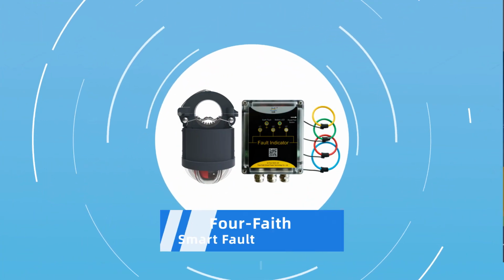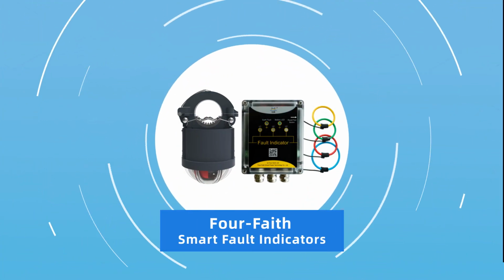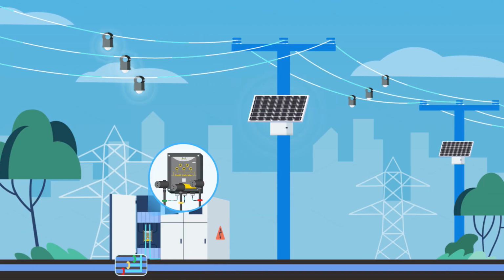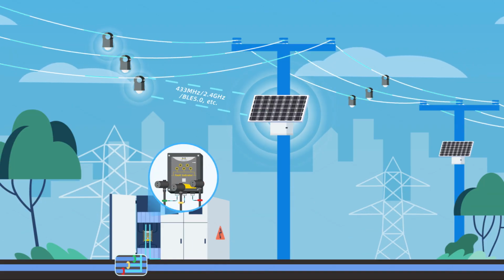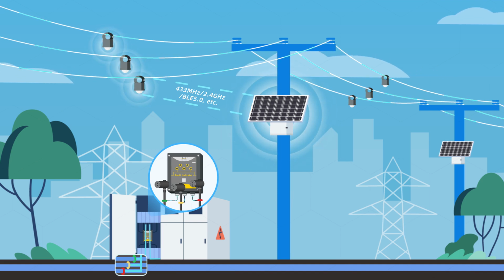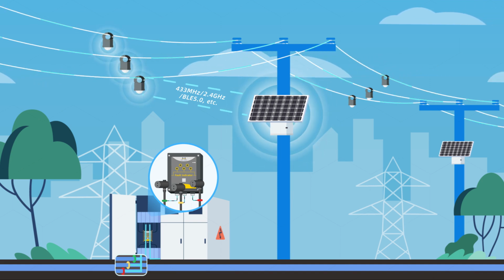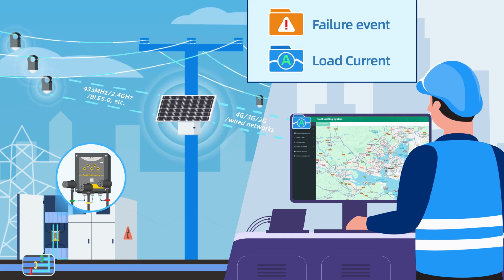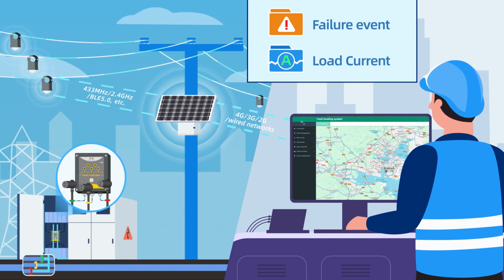As the main product for locating faults in distribution medium voltage lines, Four-Faith JYZ series smart fault indicators use short-range wireless radio frequency technology to communicate with the DCU. The DCU, by cellular networks and wired networks, uploads line load status and fault events to SCADA in real time.